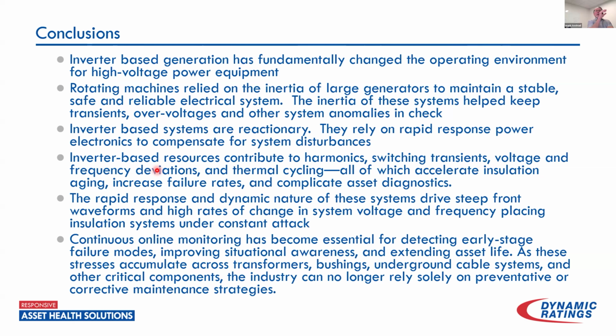And when the problem goes away, it still needs time to turn that response off. All of this can cause, again, voltage transients and frequency deviations on the system, and cause additional stress in our high voltage assets, driving thermal cycling, insulation degradation, as well as dielectric problems within the insulation. The rapid response of these systems creates steep front waveforms and high rates of change in voltage and frequency, which again puts the insulation under constant attack.